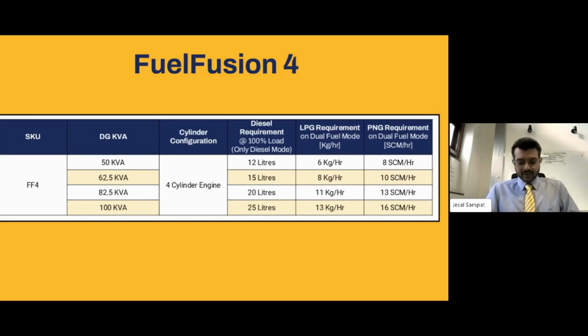Now in the table, you will also be able to see what is the diesel requirement at 100% load. For example, for the 50 kVA generator, the diesel requirement on 100% will be 12 liters, and corresponding columns you will be able to see the LPG requirement on dual fuel mode or the PNG requirement on the dual fuel mode in case you're using PNG. Now what this means is, let me explain to you very simply. If there is a 50 kVA generator, currently on 100% load, you will be using 12 liters of diesel per hour. However many hours the generator runs, 12 liters per hour will remain constant.